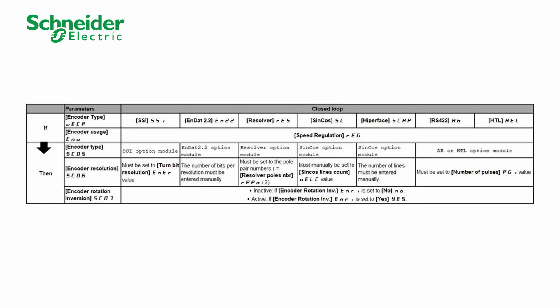This second table shows the required safety configuration depending on the type of encoder module. In case of open loop control law, only the parameter encoder type SC05 must be configured. It needs to be set to No Encoder Used. Our example is identified by the red rectangle. It gives the required value of the safety parameter to be consistent with the drive configuration.